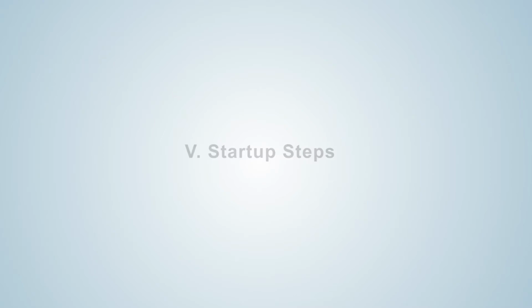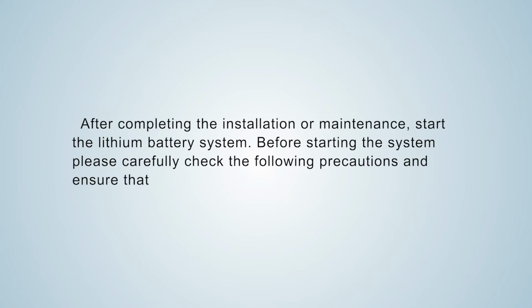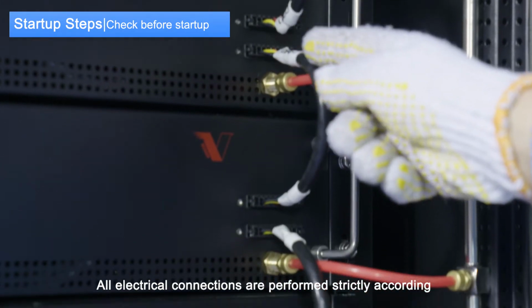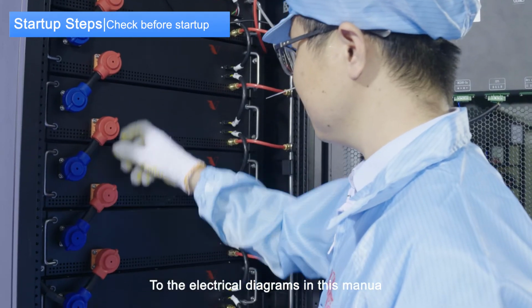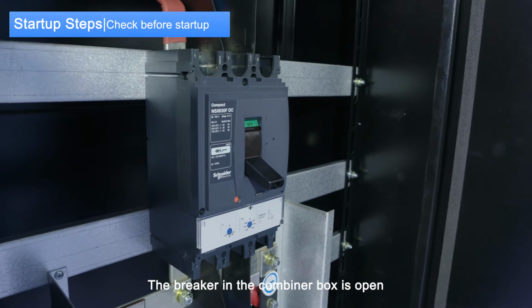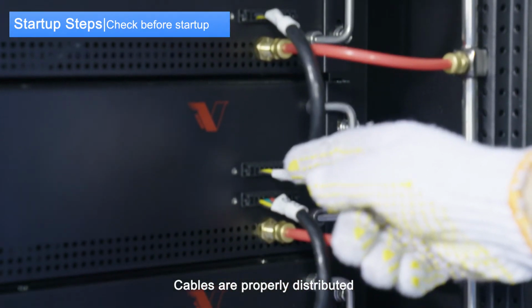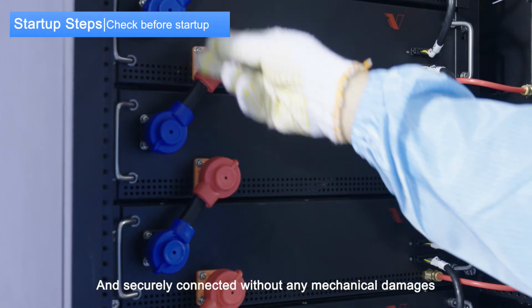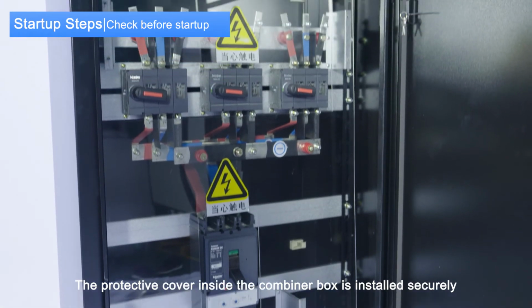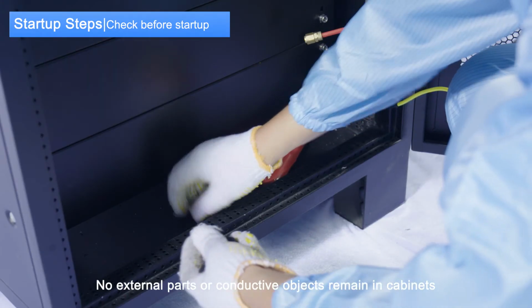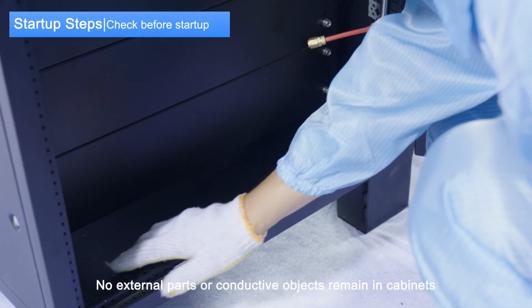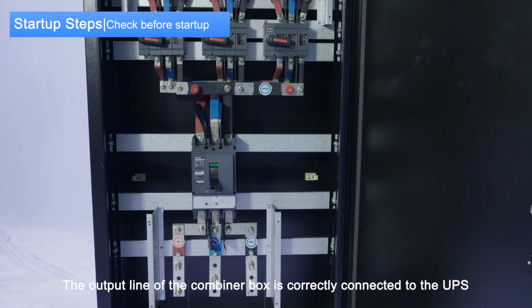5. Startup steps. Step 1. Check before startup. After completing the installation or maintenance, start the lithium battery system. Before starting the system, please carefully check the following precautions and ensure that 1. All electrical connections are performed strictly according to the electrical diagrams in this manual. 2. The breaker in the combiner box is open. 3. Cables are properly distributed and securely connected without any mechanical damages. 4. The protective cover inside the combiner box is installed securely. 5. No external parts or conductive objects remain in the cabinets. 6. The output line of the combiner box is correctly connected to the UPS.